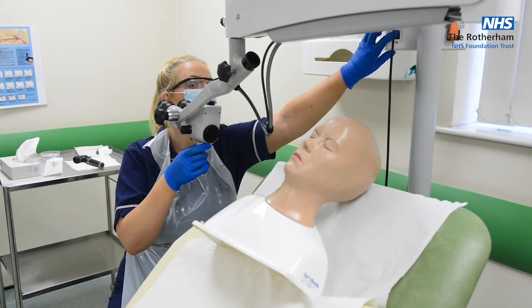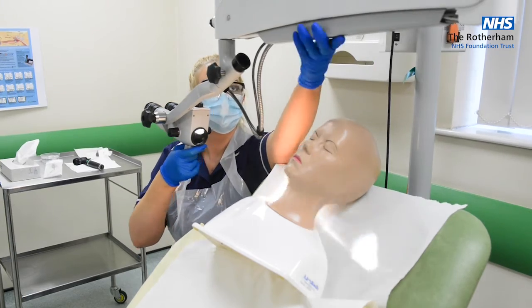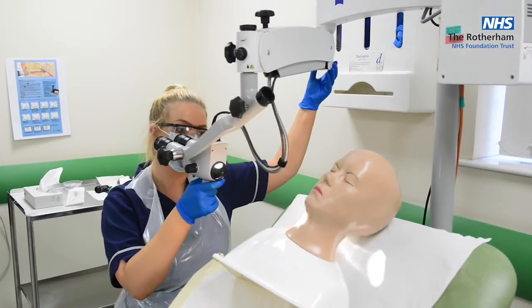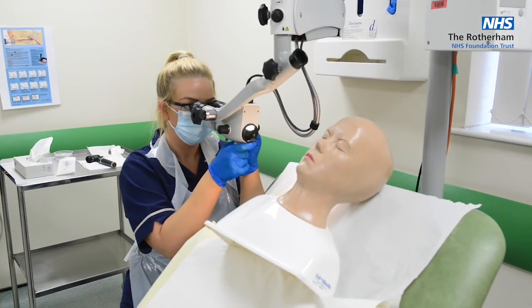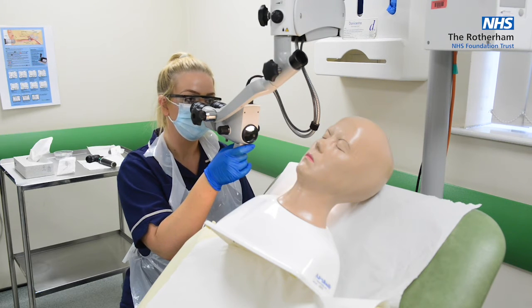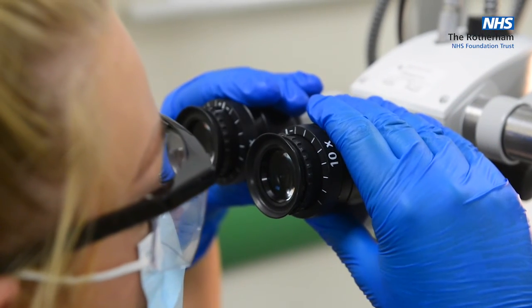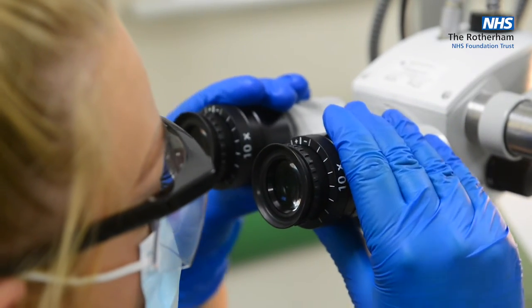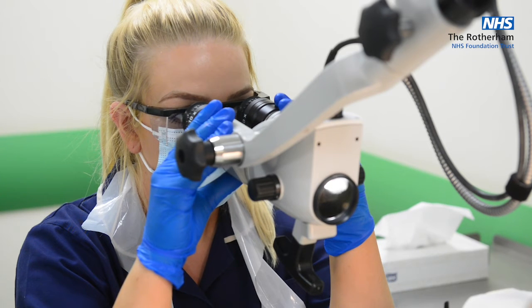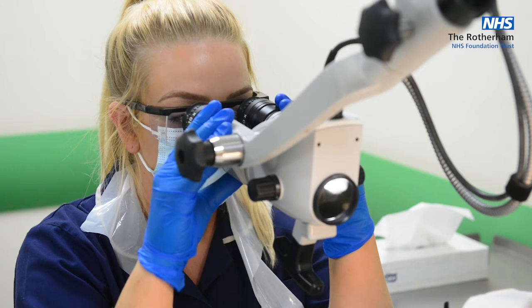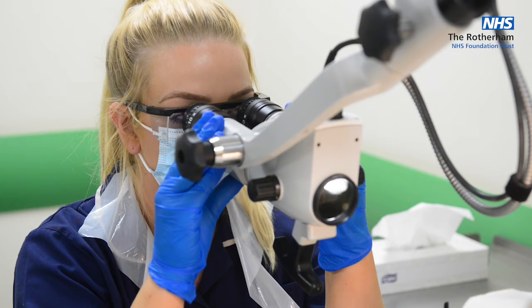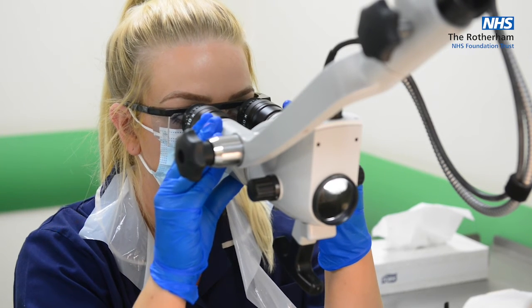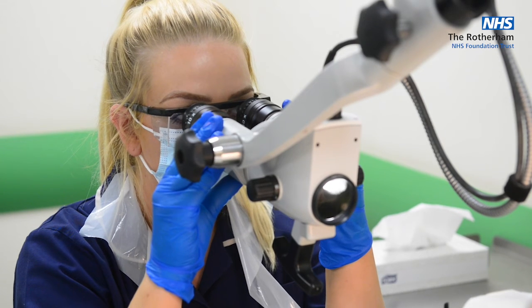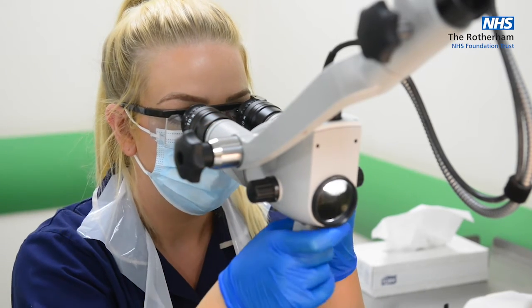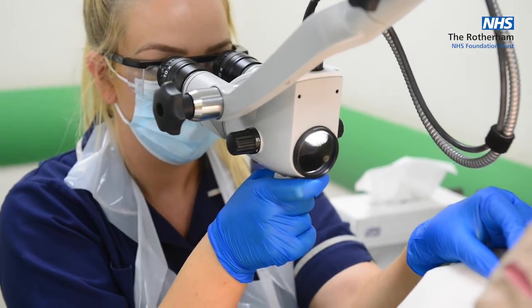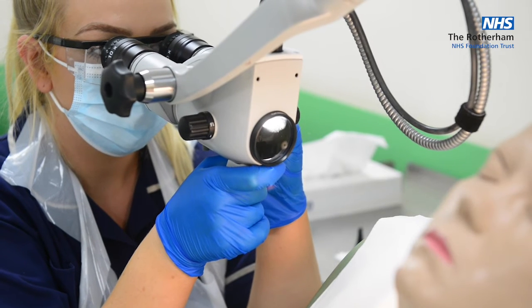Switch on the microscope, ensuring that the arm of the scope is behind you and not over your patient. If the microscope is left in this position, should the hydraulics fail, the arm will fall and injure your patient. The eyepieces can be opened and closed like so. Each individual's eyes are different widths apart, and the movement of the eyepieces allows the practitioner to adjust the microscope to the appropriate distance. Looking down the microscope, you can see one circular image. If you do not see one full circle, you may need to adjust the eyepieces further. You can then use the handle under the microscope, moving inwards and outwards to obtain a good focus. This can take some practice.